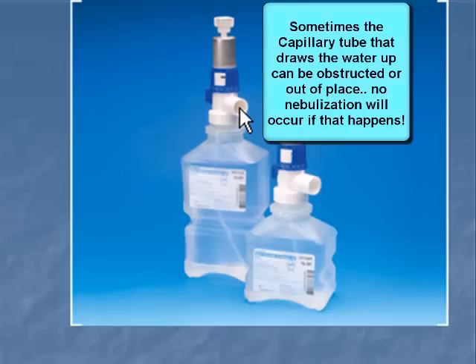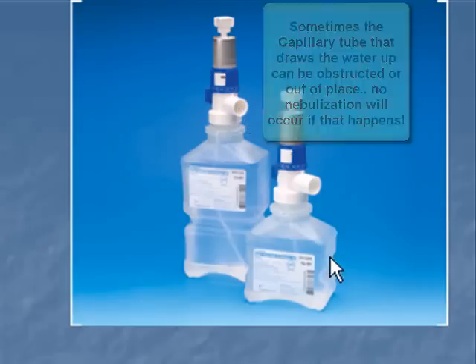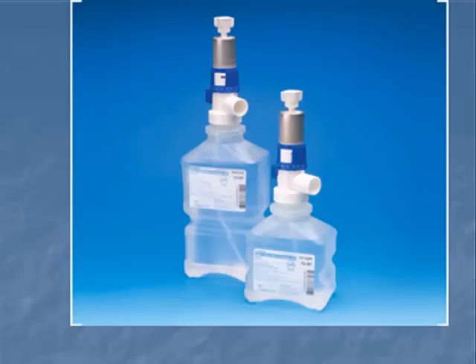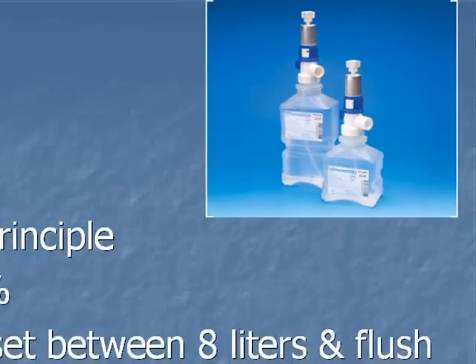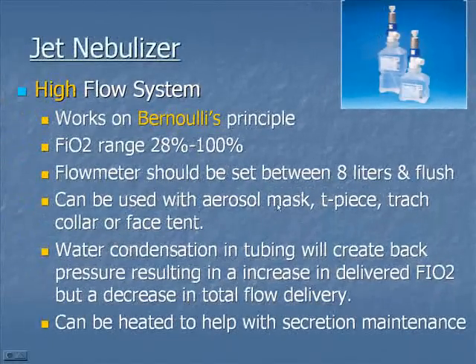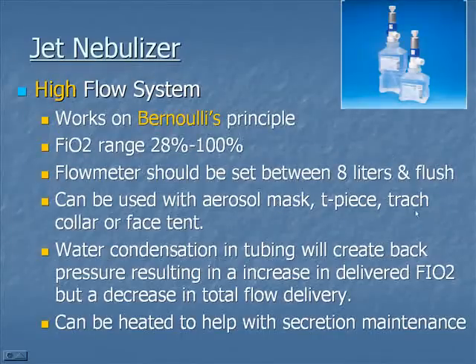You should run jet nebulizers at least 8 liters per minute — you need at least 8 liters to power the jet. If run less than 8 liters, you won't get proper mist. Always check that you see a mist before putting it on the patient. You can use these with an aerosol mask, a T-piece for a trach, a trach collar, or a face tent. Water will collect in the tubing, causing back pressure on the jet and air entrainment port — any back pressure means less room air will be entrained, raising the delivered FiO2.